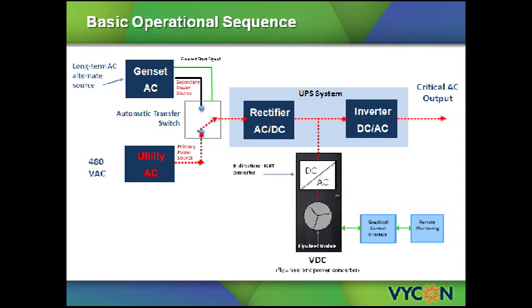As shown during normal utility operation, the output of the ATS is fed into the UPS, where the power is rectified from AC to DC and then converted from DC back to a clean, regulated AC voltage that is delivered to the critical load. The Vycon VDC connects to the DC bus of the UPS system.